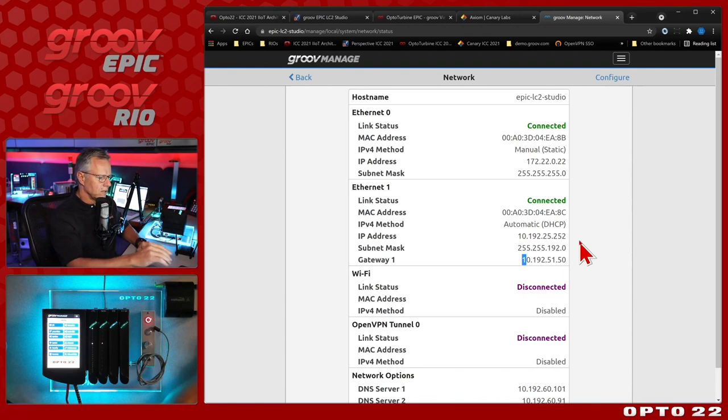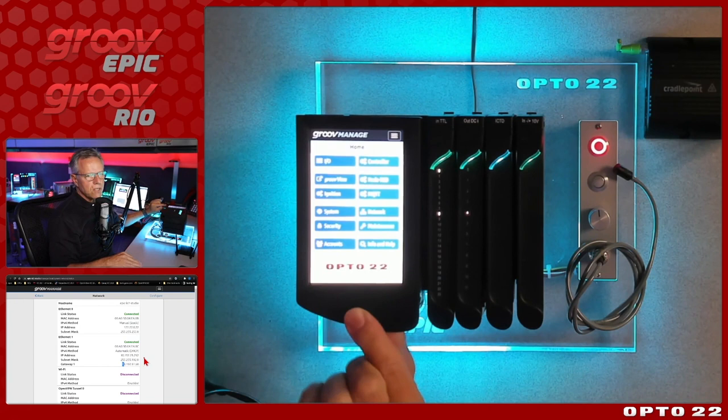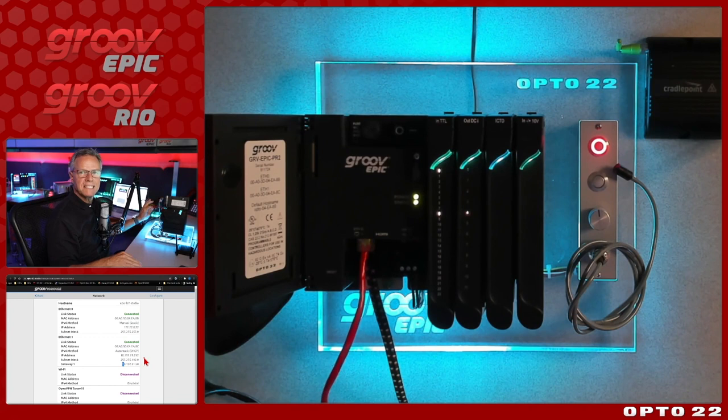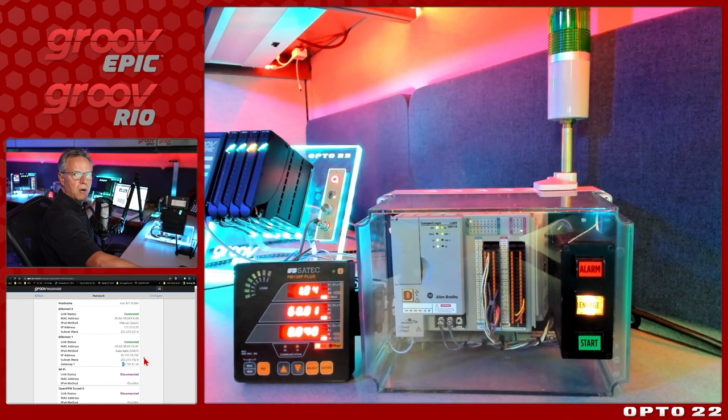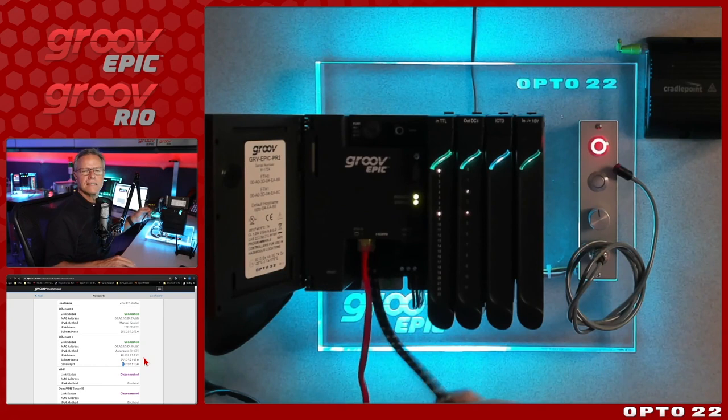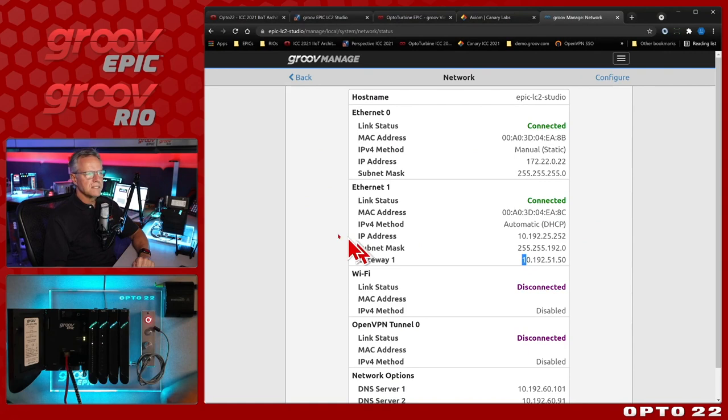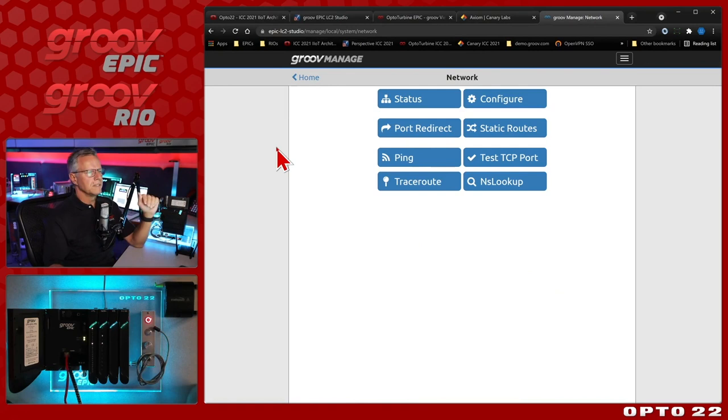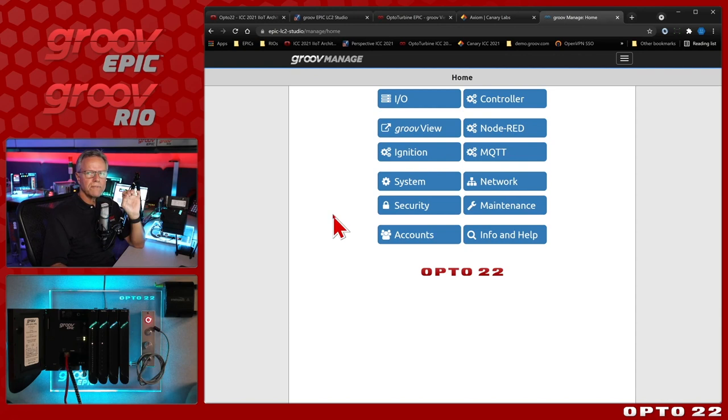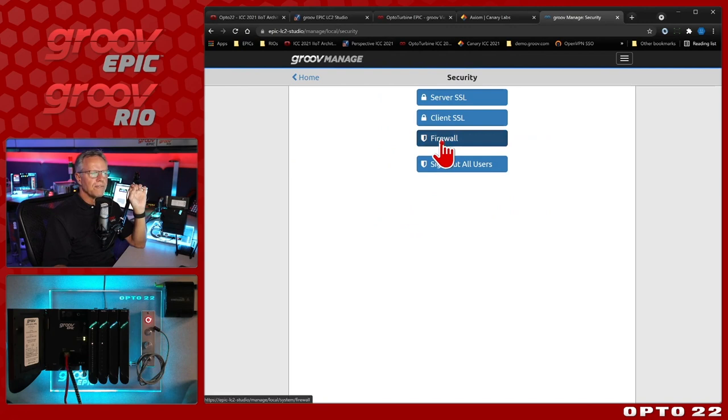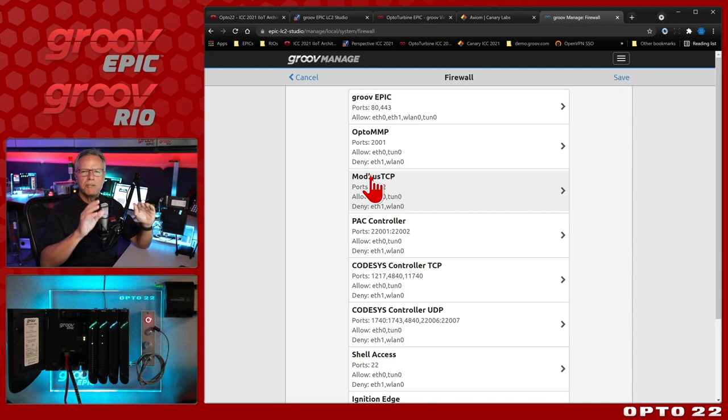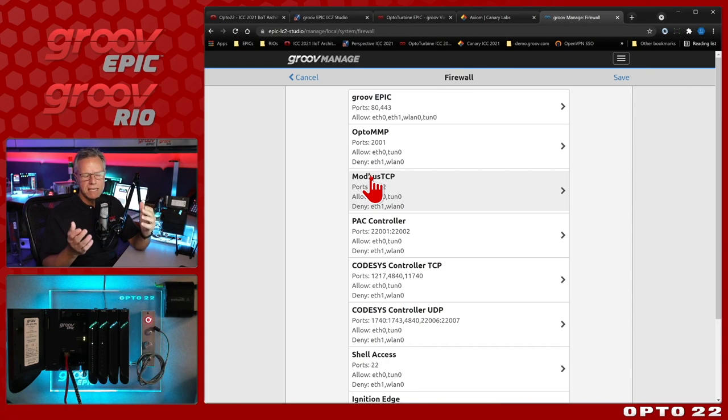Let's take a closer look at what that looks like from a physical perspective. Here's my Epic again. I'll open up the front cover and you're going to see two Ethernet cables. The red one is my Ethernet Zero which is my OT LAN, and it connects to these PLCs and Modbus TCP device behind me. The other cable is connected to my IT LAN. So the Epic is effectively segmenting or zoning those two networks completely apart and protecting those PLCs on the back end. That's essentially the networking features we have set up. But there's one other thing that's really important, and that is the firewall. There is a firewall built in for all the interfaces, so I can actually be very granular in what services I will expose to any given network interface. Simply said, on the IT LAN side I want to be very careful to only permit connections to the Epic that are authenticated and encrypted. The groov EPIC Manage software is, so I will allow it on all ports. However, maybe the CodeSys controller, the real-time control engine that's running on this - we don't want to allow access from the IT LAN, so you simply turn off that firewall port. The Ignition Edge software does permit secure connections, so we'll allow that from the IT LAN ETH1. The firewall settings are very important for making sure we're only allowing the appropriate access on secure channels.